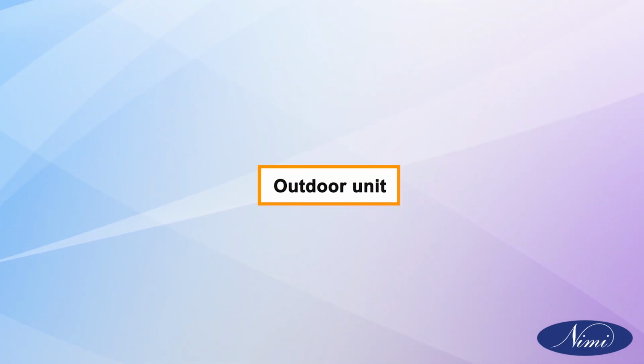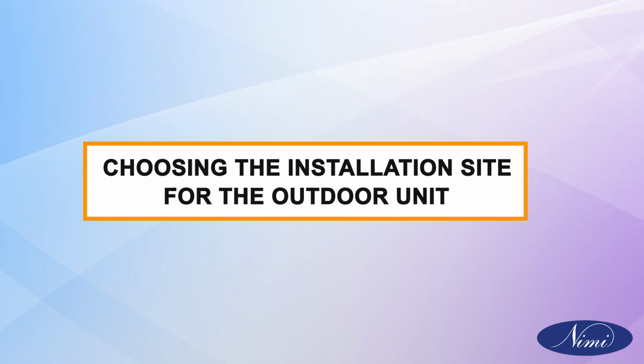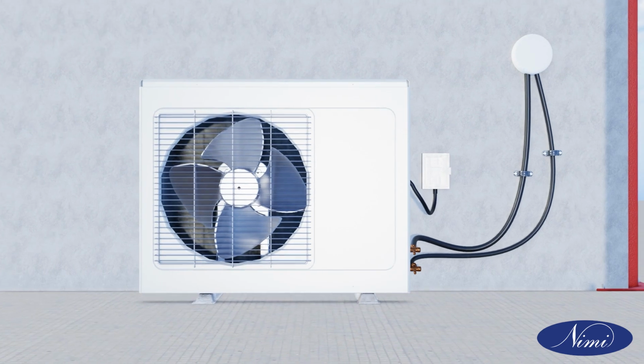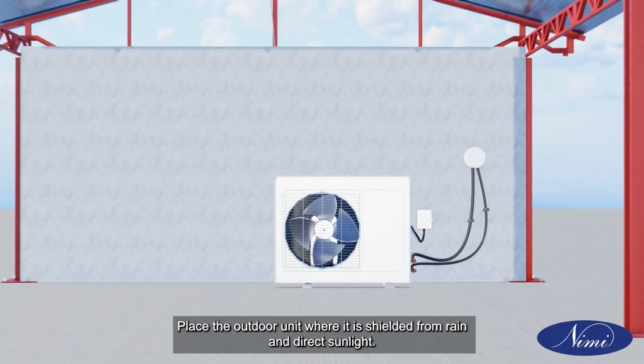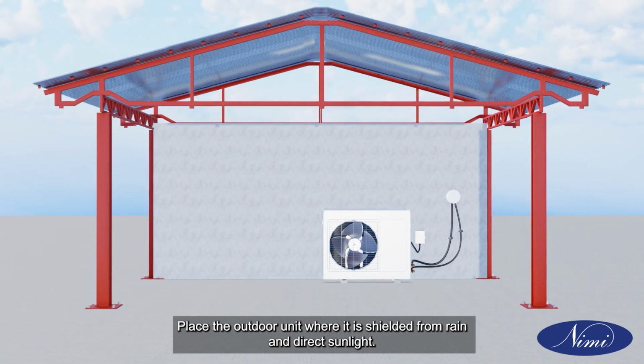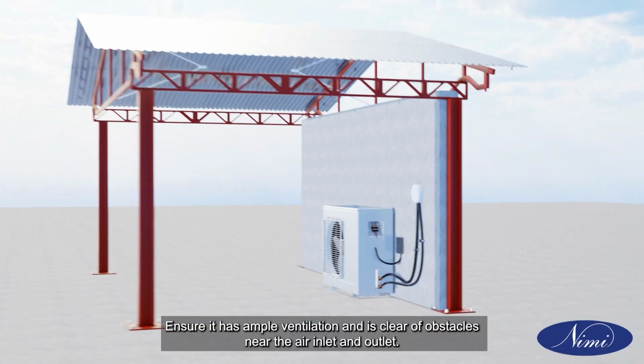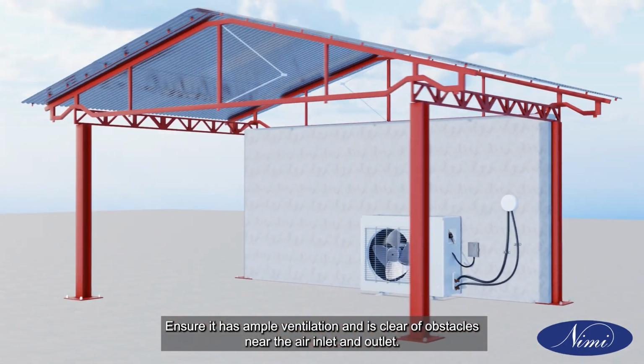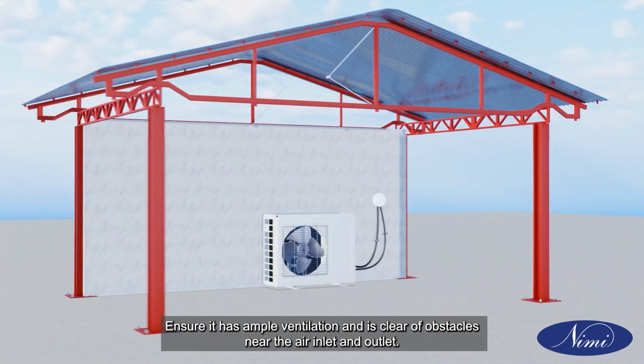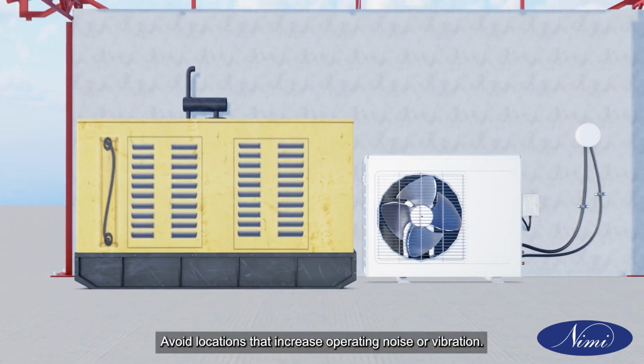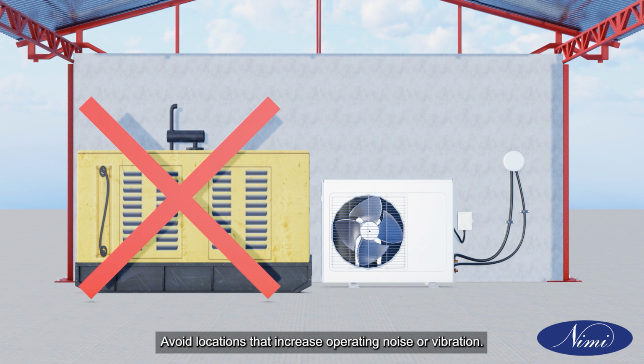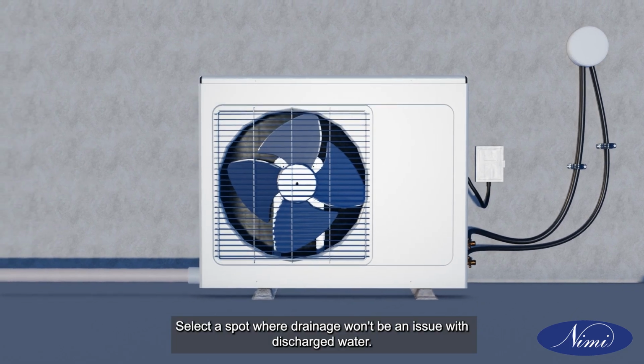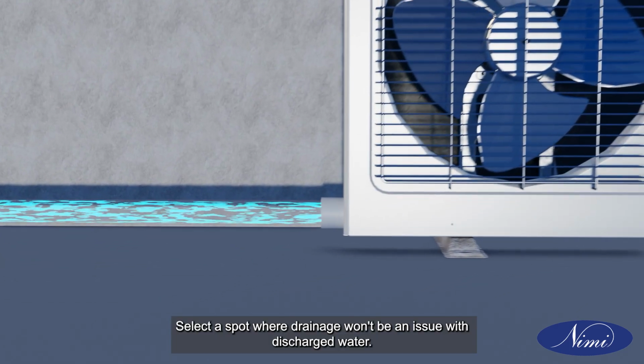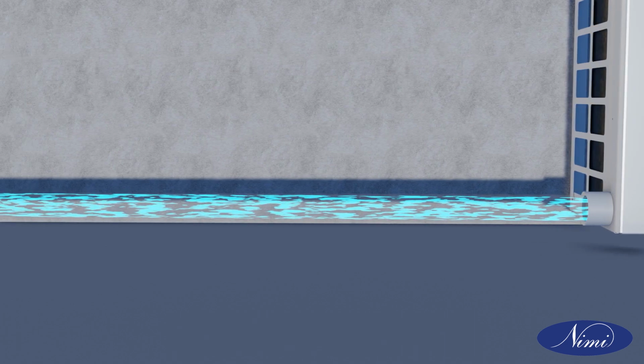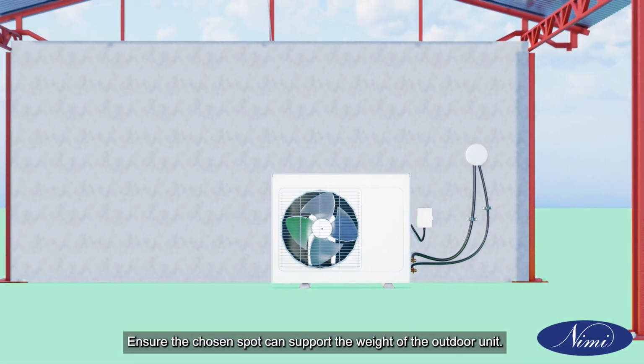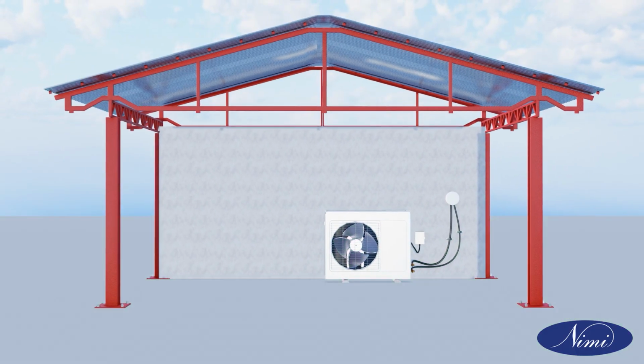Outdoor unit. Choosing the installation site for the outdoor unit. Place the outdoor unit where it is shielded from rain and direct sunlight. Ensure it has ample ventilation and is clear of obstacles near the air inlet and outlet. Avoid locations that increase operating noise or vibration. Select a spot where drainage won't be an issue with discharged water. Ensure the chosen spot can support the weight of the outdoor unit.